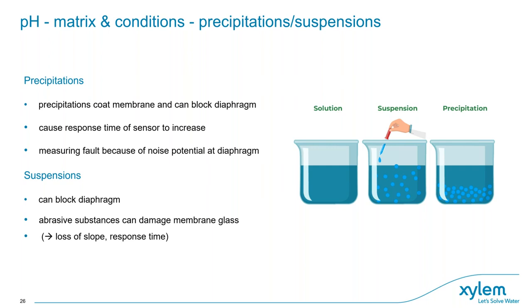Precipitations in the sample can coat the glass membrane and block the diaphragm, causing at least an increase in response time. Blocking of the diaphragm can be reduced or avoided by choosing a suitable diaphragm type with a higher sustainable flow rate. Suspensions can also block the diaphragm — using an electrode with a different diaphragm can help. Abrasive substances like sand can damage the membrane by grinding, especially with high flow or high stirring rates.